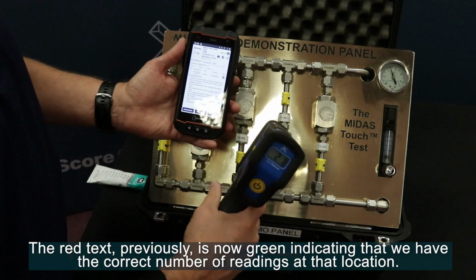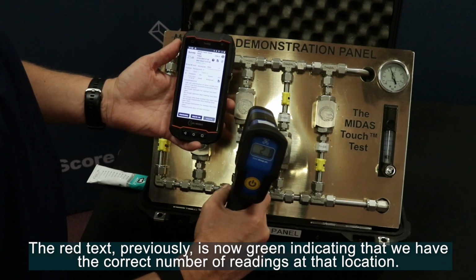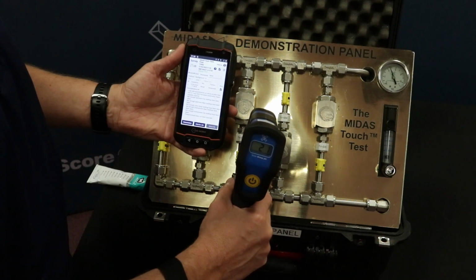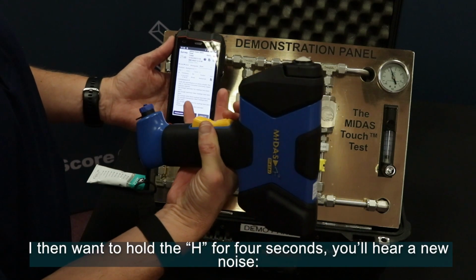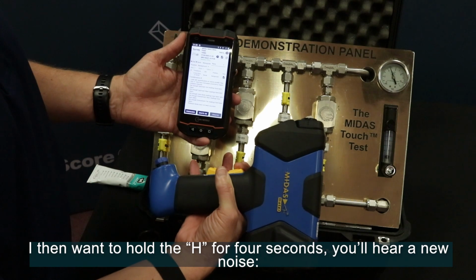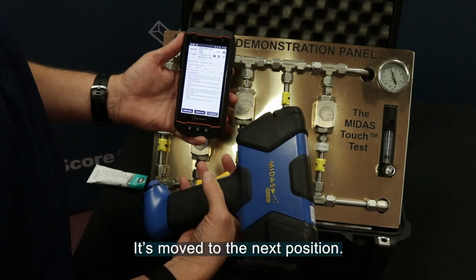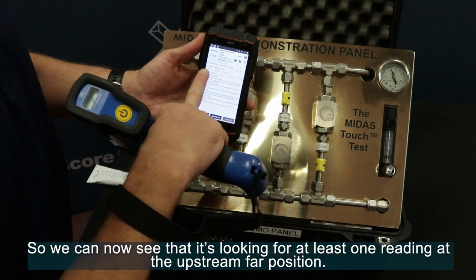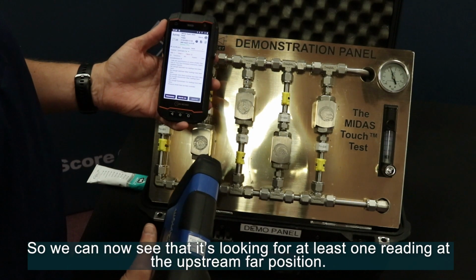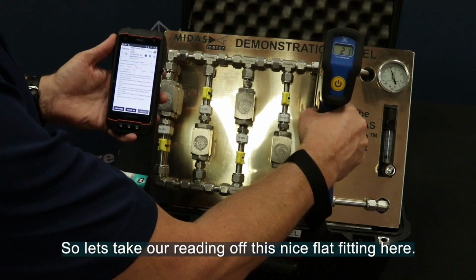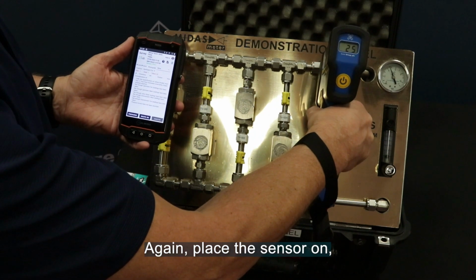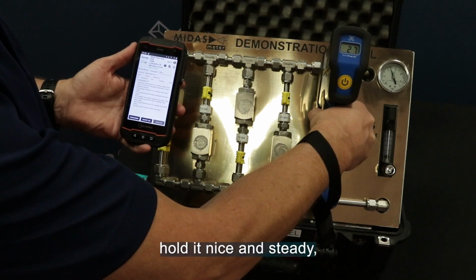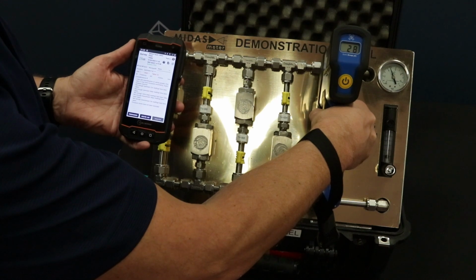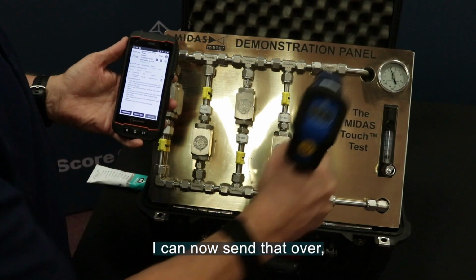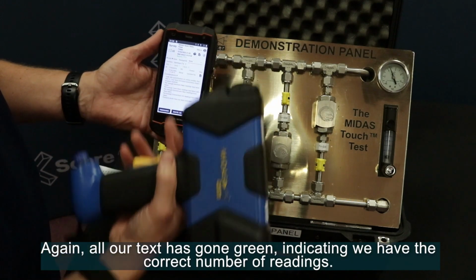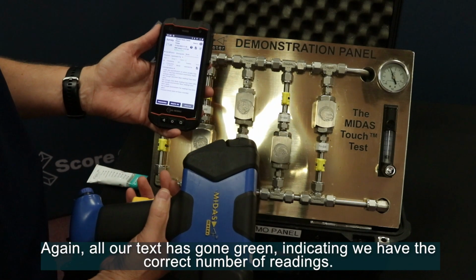The red text previously is now green, indicating that we have the correct number of readings at that location. I then want to hold the H button for 4 seconds, and you'll hear a new noise. It's moved to the next position. So we can now see that it's looking for at least one reading at the upstream far position. So let's take our reading off this nice flat fitting here. Again, place the sensor on, hold it nice and steady, wait for the number to stabilize. 28 decibels is stable. I can now send that over. Again, all our text has gone green, indicating we have the correct number of readings.